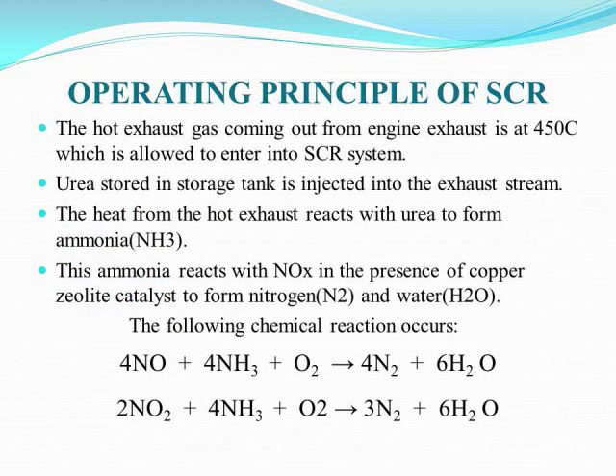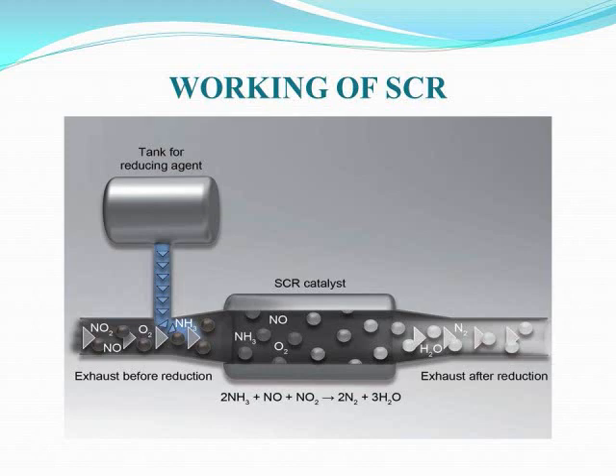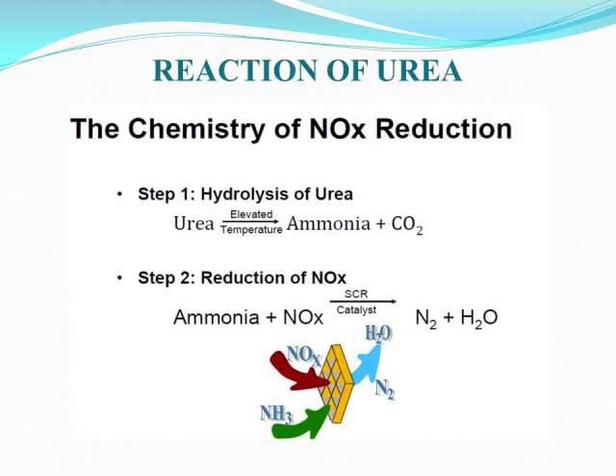Selective catalytic reduction is the process in which oxides of nitrogen in diesel exhaust are reduced to nitrogen and water by injecting ammonia into the exhaust. 'Selective' means targeting NOx in the diesel exhaust. 'Catalytic' means it requires a catalyst — we are using copper zeolite catalyst, chosen over vanadium pentoxide, platinum, rhodium, and palladium because it is cost-effective, cheaper, and can operate at higher temperatures. 'Reduction' means NOx is reduced to nitrogen.